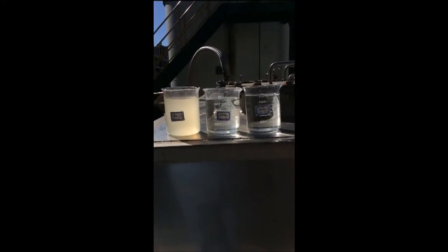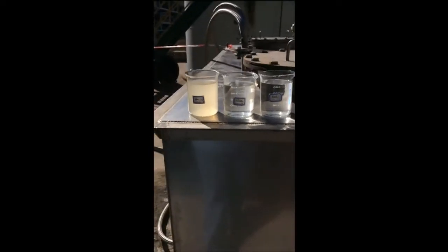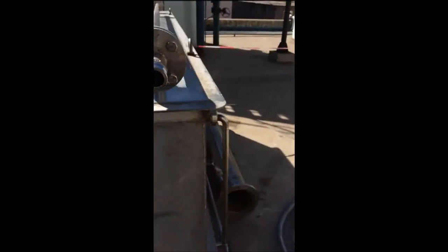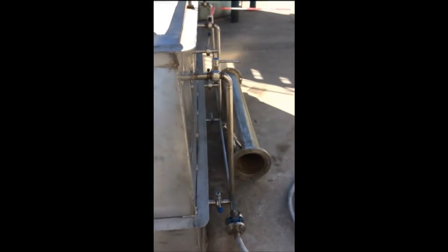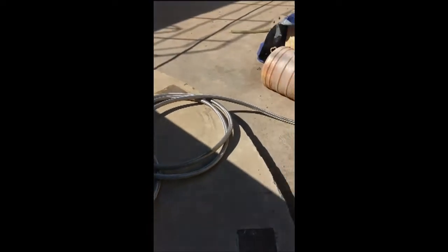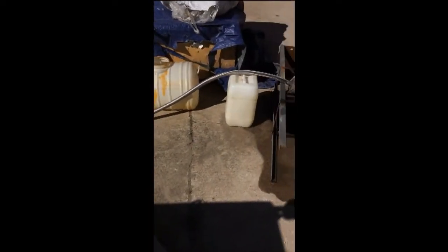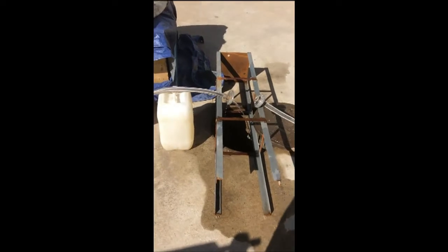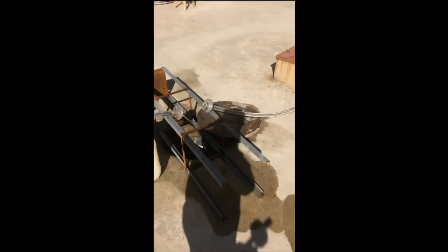On the left is the raw water going in. The center is the flotation water coming out of the flotation cell, and then the water coming out of the membrane bundle. As I said, about 150 NTU, 4 NTU, and less than 0.2 NTU. Now you can see that the water here is running on a continuous basis, and that water is now being discharged back into the refinery's cooling water return system.